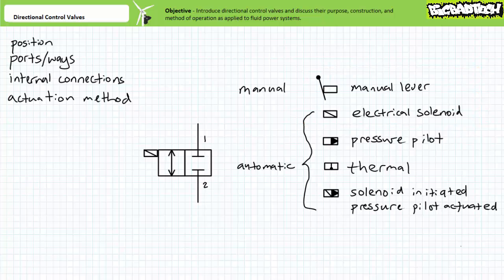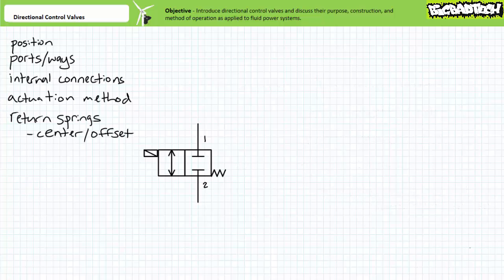A manual lever-operated valve requires an operator to physically push or pull the valve into a new position. A solenoid-operated valve uses an electrical solenoid, a type of linear electrical actuator, to physically push or pull the valve into a new position. We'll deal with some of the electrical characteristics of solenoid-operated valves in later lectures. Valves use return springs that either offset or center a valve to an initial deactivated position. This example valve is spring offset into the normally closed position such that the valve does not ordinarily conduct fluid.